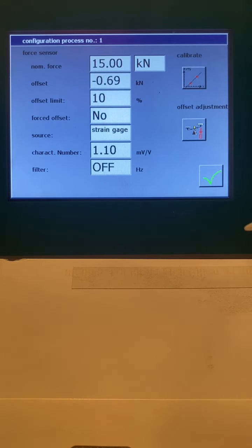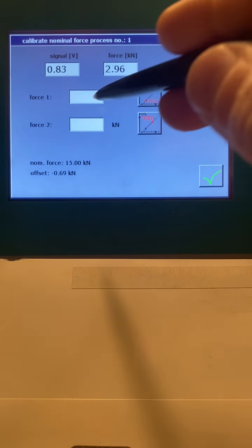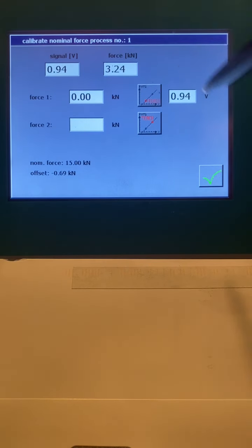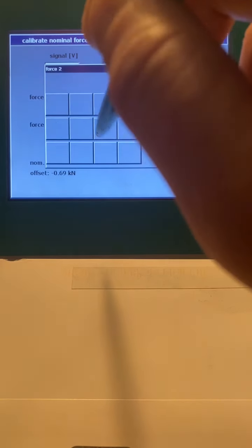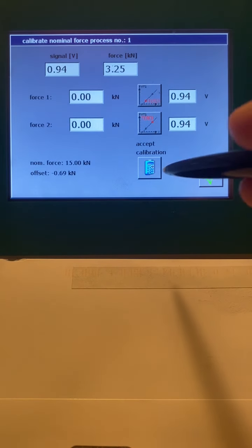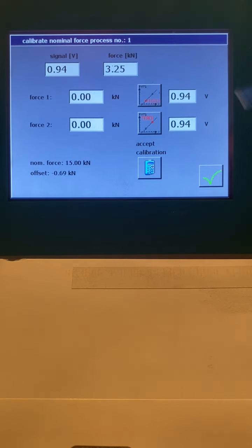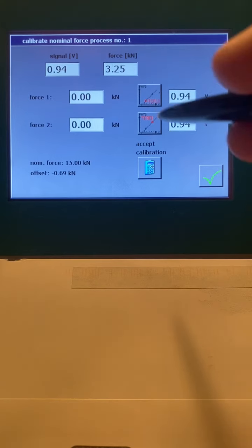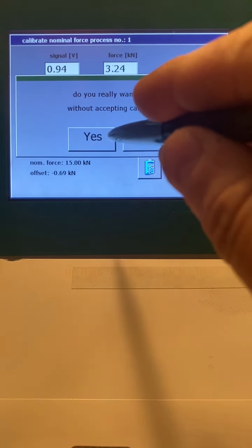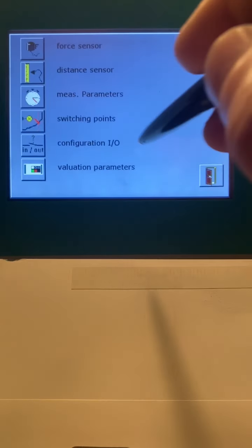So when I'm setting this up, typically we want to do a 2-point calibration, and you hit this button here, and you're going to get a 2-point calibration. Let's say I type in 0, and then I hit teach. It just grabbed, hey, 0.94 volts is 0. And then I can type in 0 again and hit teach. And then I can accept the calibration. So this is a way that you would do a 2-point calibration. Yes. I'm going to save this for this process.